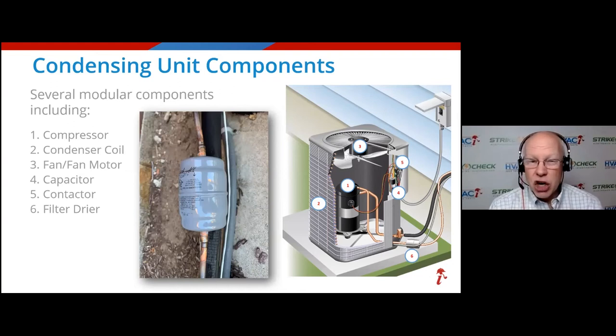It's basically like filtering your oil in your car. This is in the refrigerant line and it's filtering the refrigerant. These systems must have clean refrigerant to operate properly and not damage your compressor, okay? The one thing I'll say about these is they show up on estimates and reports like ours sometimes when they weren't damaged. And I'll tell you why. If we have to open up this unit for any reason and work on it, like take out the refrigerant to put in a new compressor because it got fried by a surge, you're going to see on that report a new filter dryer, even though it wasn't damaged. Because like your car, if I put new oil in it, I'm not going to then drive it with an old filter. That just doesn't make sense, right? Same thing. You don't take refrigerant out and put it back in and leave the old filter dryer. You put a new filter dryer in. That's industry best practices. So that's why you see that.